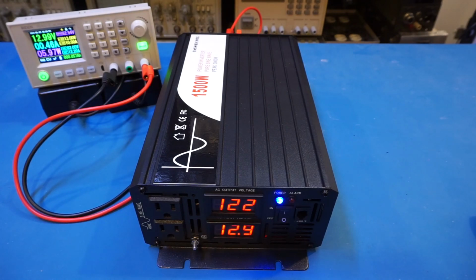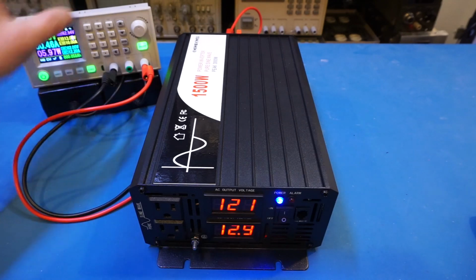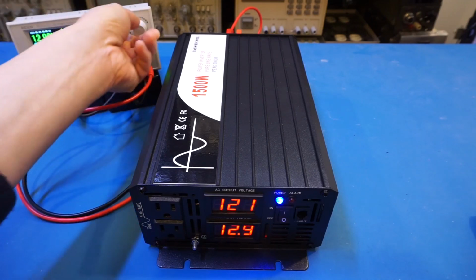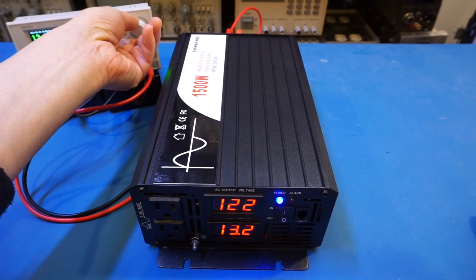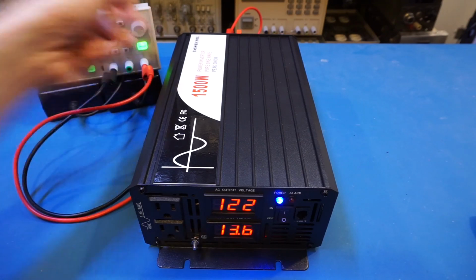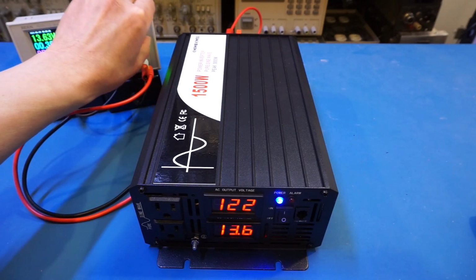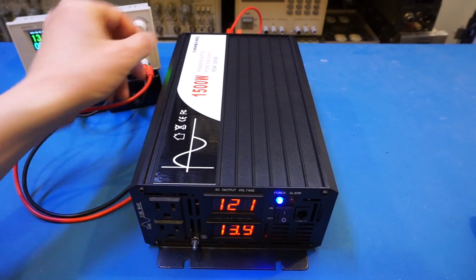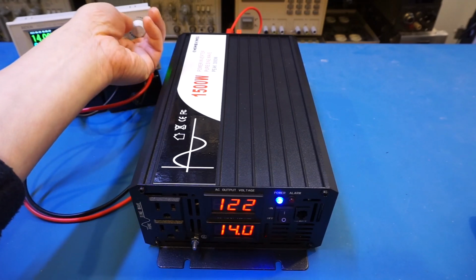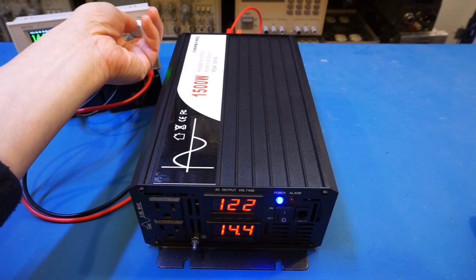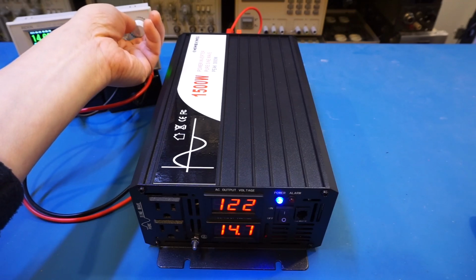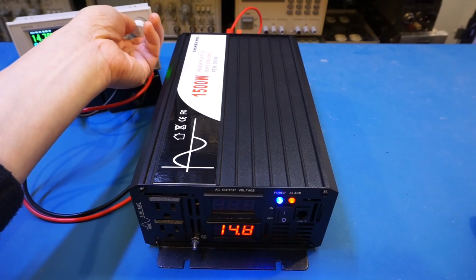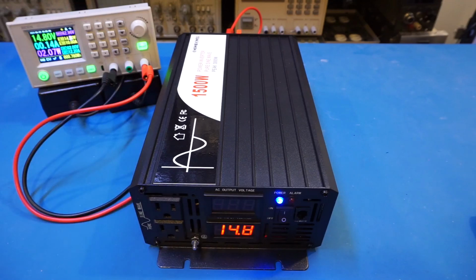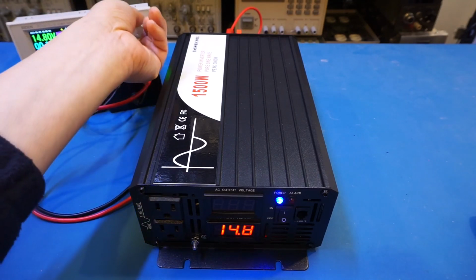Since this inverter has overvoltage and undervoltage input protection, let's see when that's triggered. I'm going to use VSET and increase it 0.1 volt at a time, starting with overvoltage. Now it's 13.6 volts, 13.8, 14 volts, 14.7. It seems like at 14.8, the overvoltage protection is triggered.